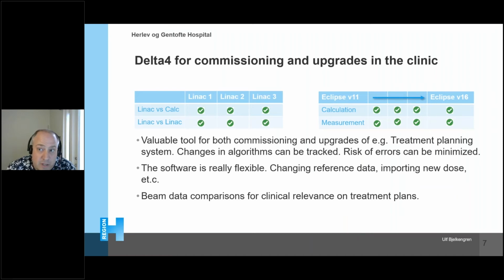Delta 4 and commissioning and upgrades in the clinic. With the Scandidos software for the Delta 4, it's really flexible, so it's easy to compare it to what you want to compare with. So we use it a lot, of course, when commissioning new machines to compare one machine to another machine, and of course the Linac versus calculation when commissioning new accelerators. What we've also been using the Delta 4 system for has been upgrades in the clinic of the treatment planning system.